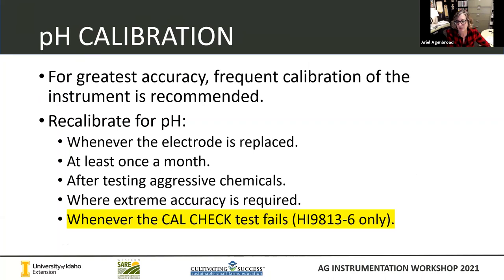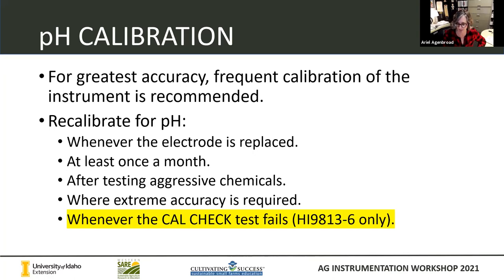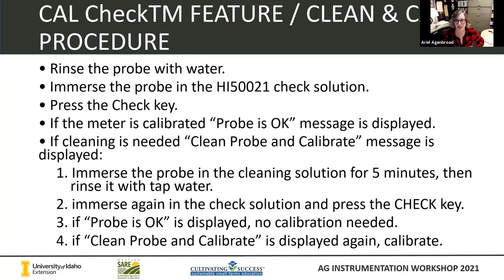We do need to calibrate these instruments for greatest accuracy. You're going to want to calibrate anytime you replace an electrode, maybe once a month if you get it out and use it frequently, if you've been testing any aggressive chemicals, or if you really want to be as accurate as possible. What we have in this model is a calibration check feature, which is really neat, so you may only need to calibrate after you've tried the cal check and it fails.